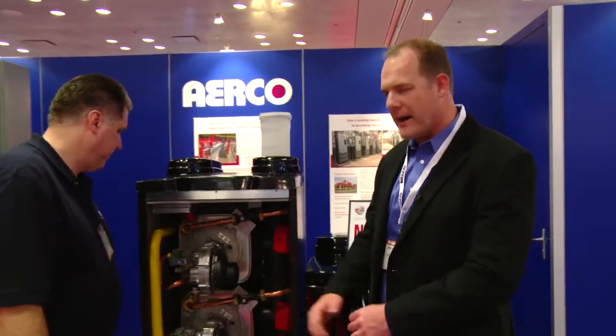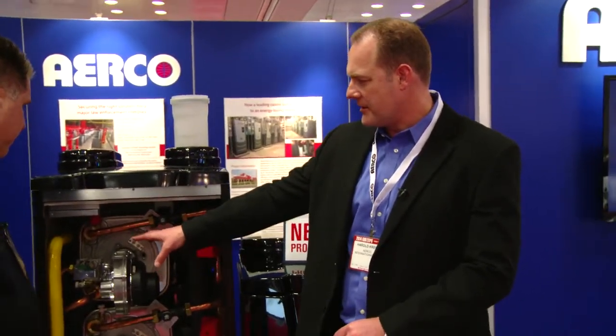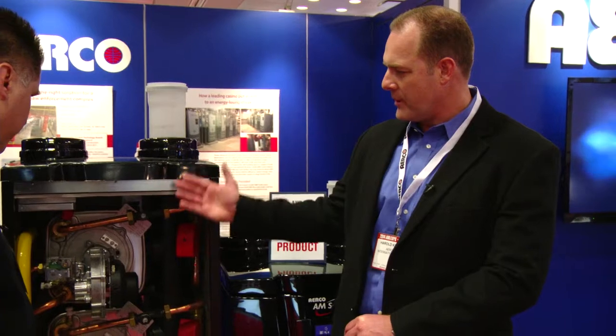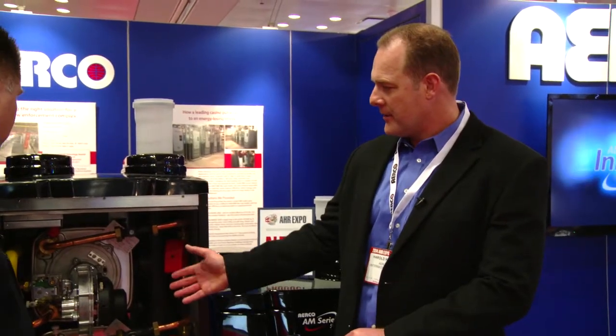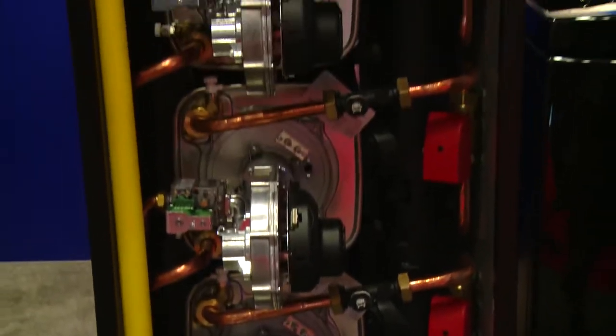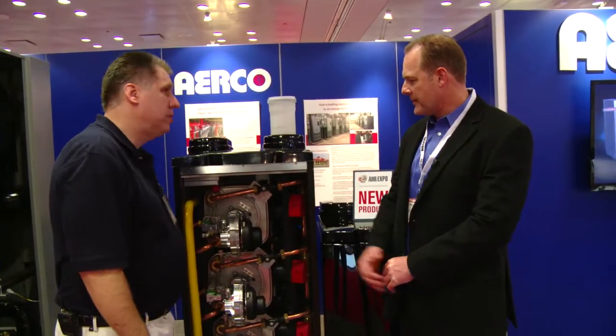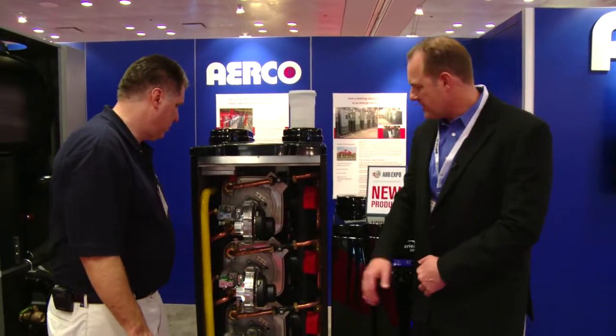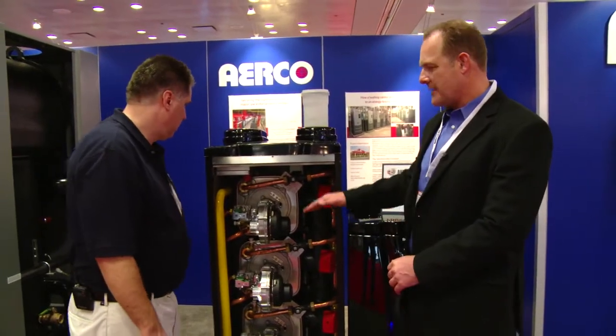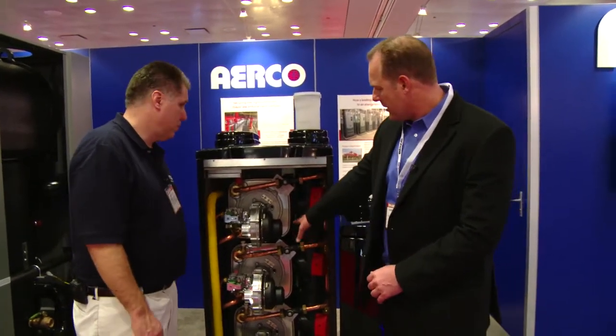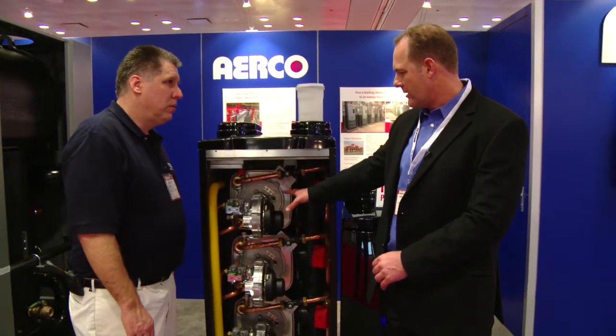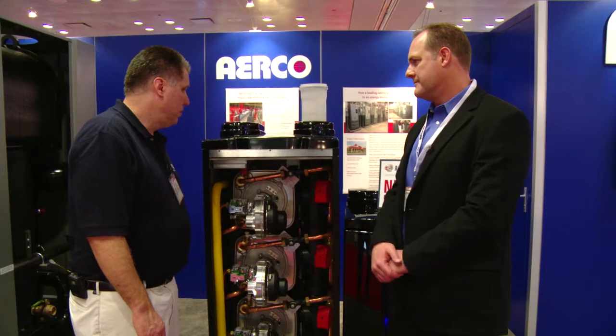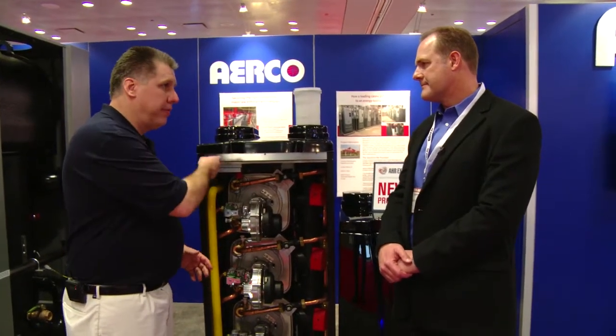Each of the heat exchangers come in modules, and on each heat exchanger is a 5-to-1 turn down gas valve. So a 1 million BTU boiler or water heater with 4 heat exchangers would have a 20-to-1 turn down ratio, giving you optimal performance and optimal efficiency. So if I'm hearing you right, not only is it staged with 4 stages, each stage modulates. Absolutely, giving you the highest turn down, as well as some limited redundancy. As you can see, each heat exchanger has a built-in control valve. So as stages are needed or not needed, the flow will be isolated to that particular coil, again, to optimize performance and increase turn down. Sure, you don't want boiler water going through an off cylinder.